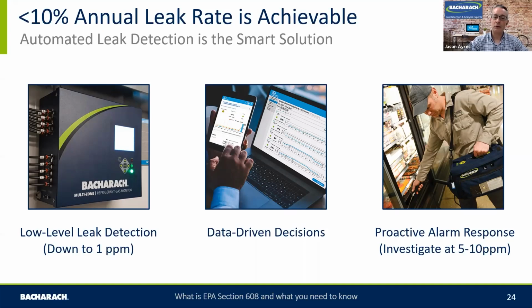If we're responding at that level, we have a sizable refrigerant leak. Let's look at moving that lower, looking at 5, 10, 20 ppm as a response to an alarm. We're not saying that at that level you should be rolling trucks, but at that point you should put a works order in and have somebody attend site to try and investigate and find these small habitual leaks before they get bigger. At that level, you will be able to locate them, but they will need to take a little bit more time. But it's all a part of this strategy to reduce your refrigerant usage.